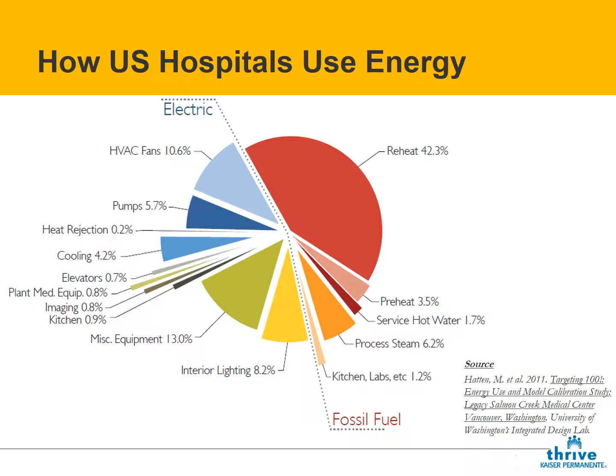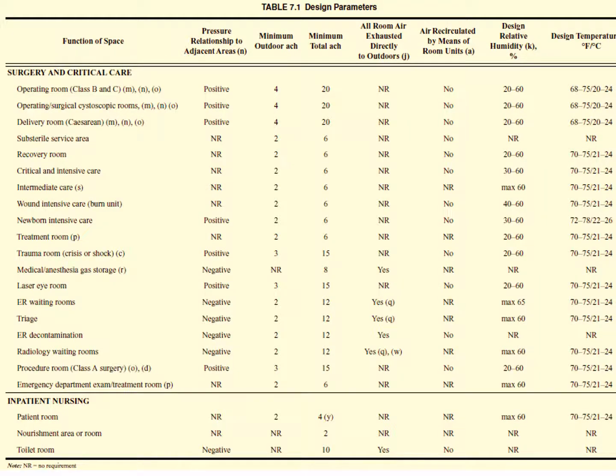It's hard to overstate how outrageous our HVAC energy use is. If you built a 200-bed luxury hotel and a 200-bed hospital right next to it, exactly the same size, the hospital's HVAC systems would use 5 times the annual energy of the hotel's. So it's not off by 20% or 30%—we're off by 500%.